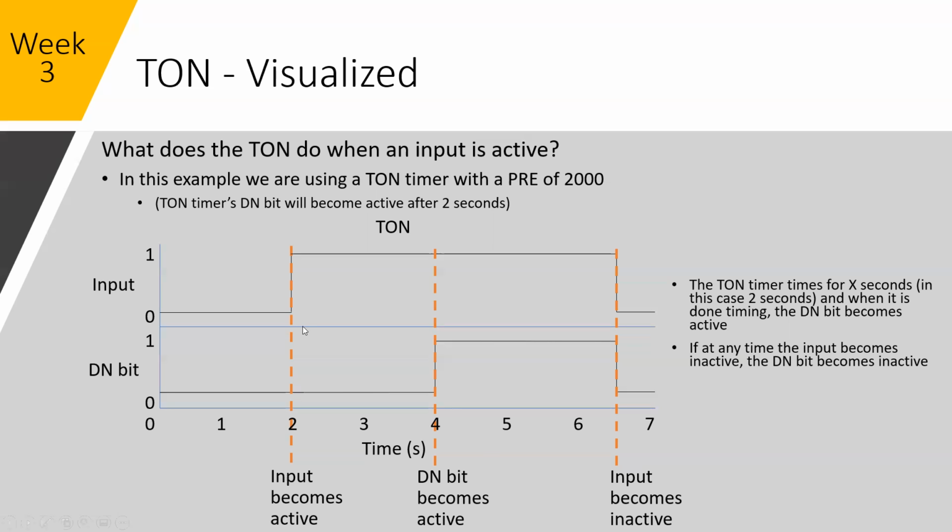If the input does not stay true for the entire duration of the preset, then the preset will reset. So if it dropped down at 3 seconds and came back on at 4 seconds, then it would wait until 6 seconds before the done bit will become true.